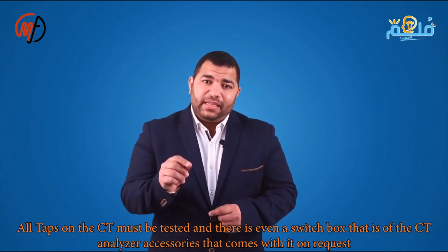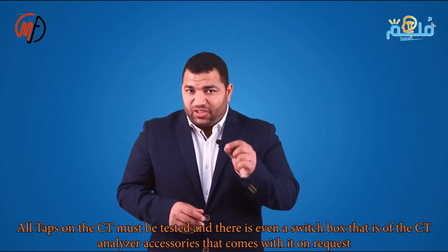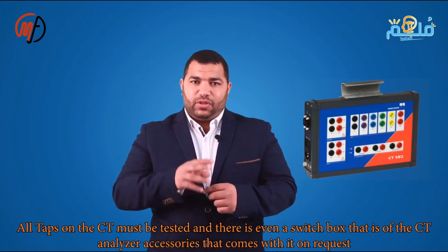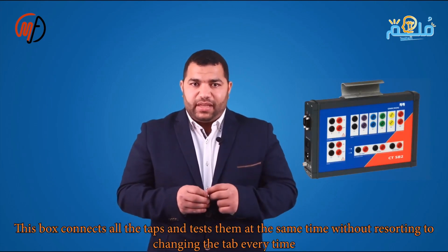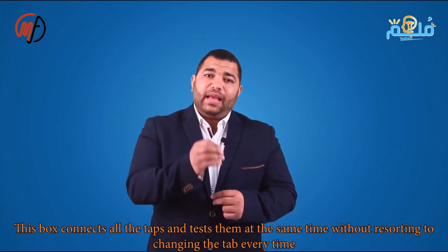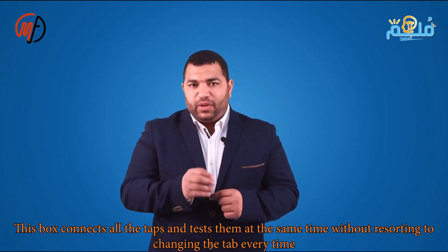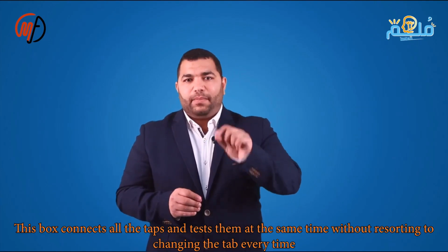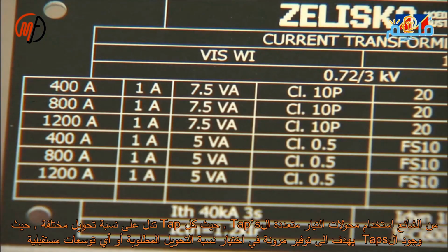All the taps on the CT must be tested, and there is a switch box that comes as an accessory with the CT analyzer upon request. This switch box connects all the taps and tests them at the same time without the need to change the taps each time.